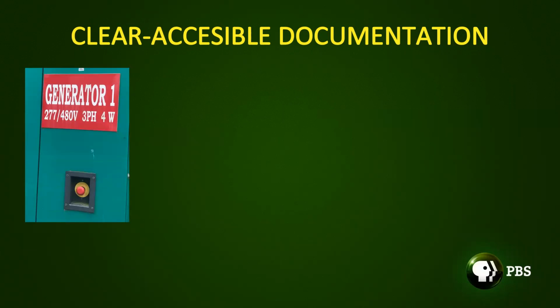This is the outside of generator number one. Well, gee, doesn't everybody know that generator number one is the one that faces east-west and generator number two faces north-south? Well, people forget, and contractors may not know that either. So this little piece of signage has saved us some pretty major problems, because it tells the electricians and generator technicians that they are working on generator one, and that generator one, when healthy, produces 277 and 480 volts, in a three-phase arrangement with a 4-wire connection. That tells the electricians almost immediately, without any doubt, what they need to look for to make sure it's performing correctly.